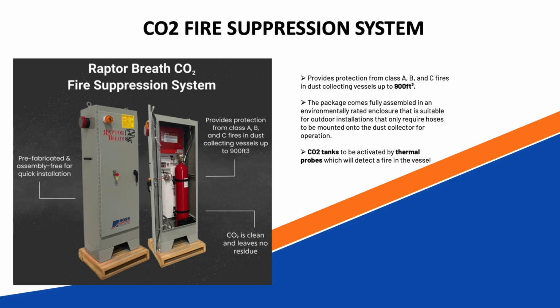Our system. Sometimes we have applications where water can't be used, whether it's because the food process can't get wet, or maybe there's no water supply for the end user. We can do a CO2 fire suppression system inside of the vessel you're trying to protect. In our solutions, we can cover up to about 900 cubic feet of vessel, and they're activated by thermal probes. Next slide, Andy.